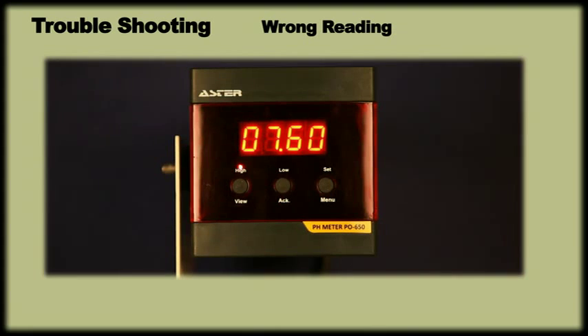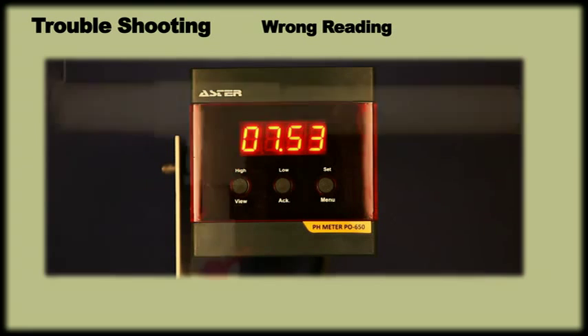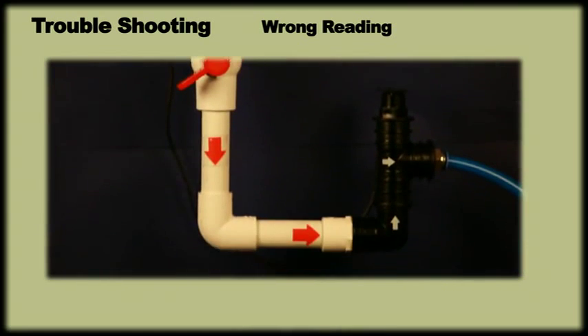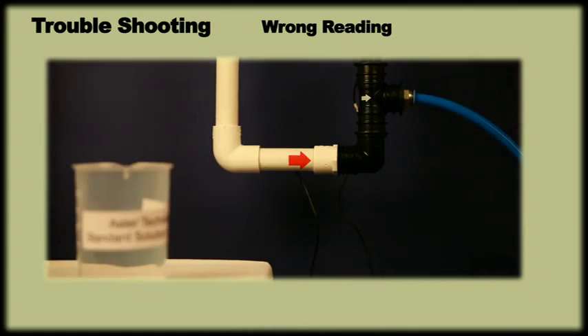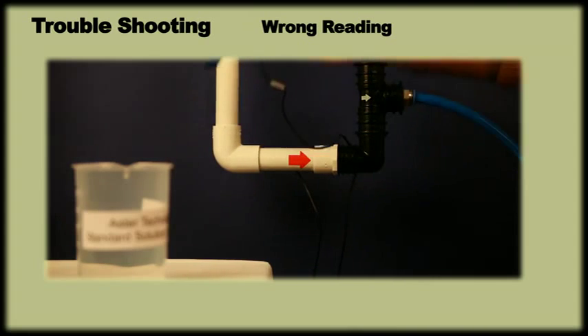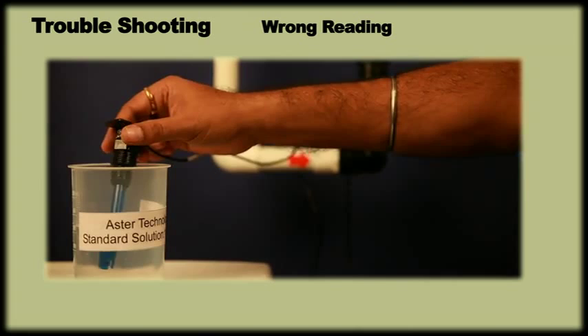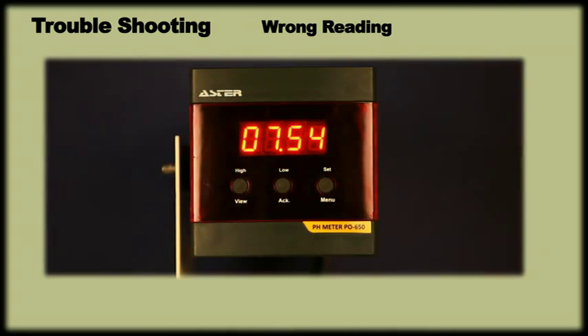If the meter shows wrong reading, it could be because of the following reasons. If the sensor is installed correctly, yet it shows wrong reading, then remove the sensor from line and test the sensor in standard solution of 7 and 4 pH. If it still shows wrong reading, then recalibrate the meter. The wrong reading could also be due to very low conductivity in the water.